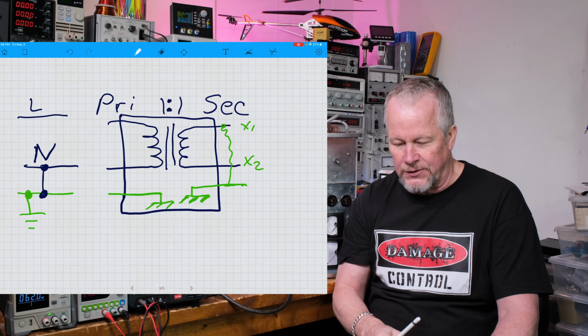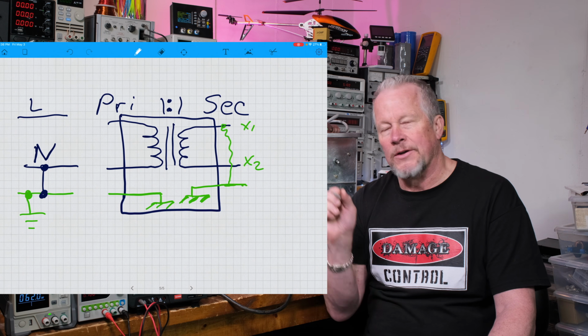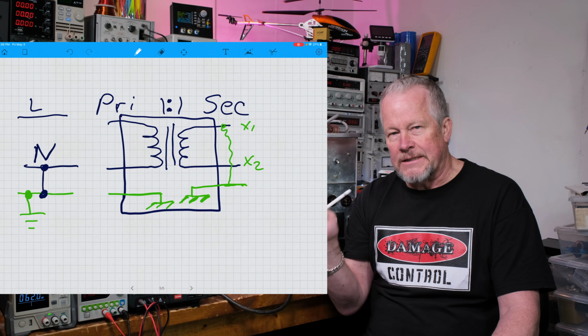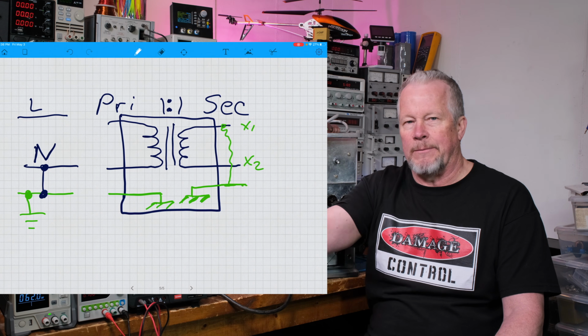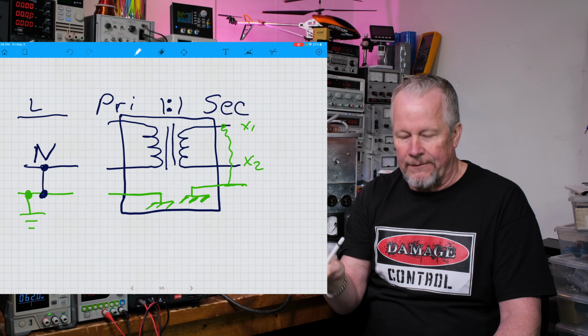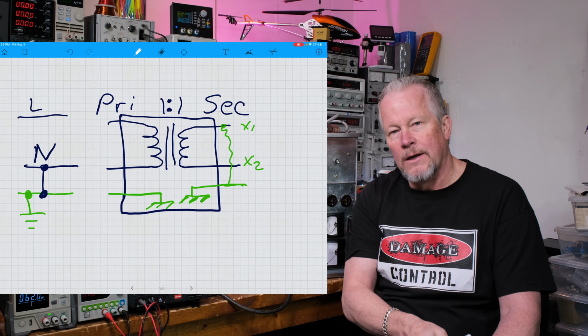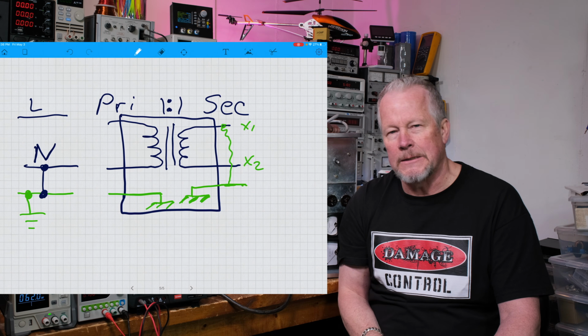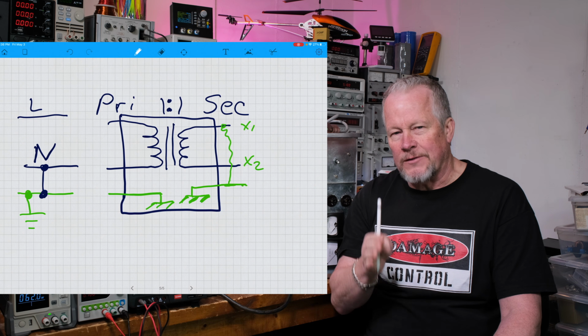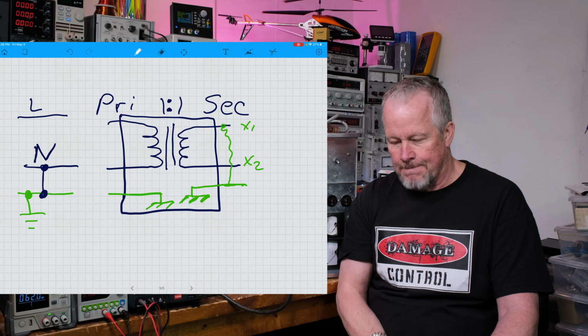Well, where does it go? There's an isolation transformer. It can go back to, it's touching the same place that the neutral and ground are bonded back there. If you ohmed them, they'd all have the same place. X1 would be ohmed to your neutral on your primary side. But the isolation transformer is still isolated, okay?